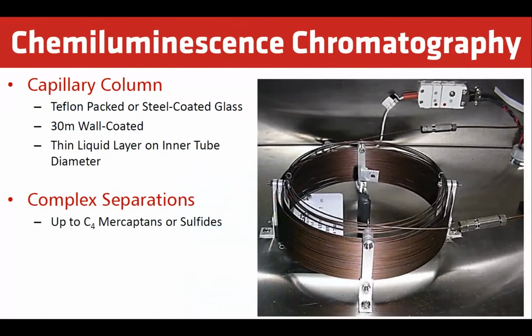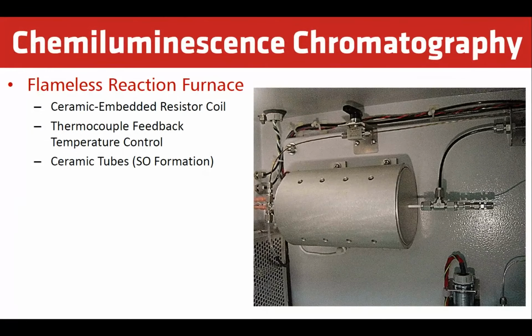The capillary column, it's Teflon packed or steel coated glass, 30-meter wall coated, thin liquid layer on the inner tube diameter. It's used for complex separation up to C4 mercaptans or sulfide. We use a flameless reaction furnace, ceramic embedded resistor coil, thermocouple feedback for temperature control, and ceramic tube for SO formation. So this is basically what we call our oxidation reduction oven.